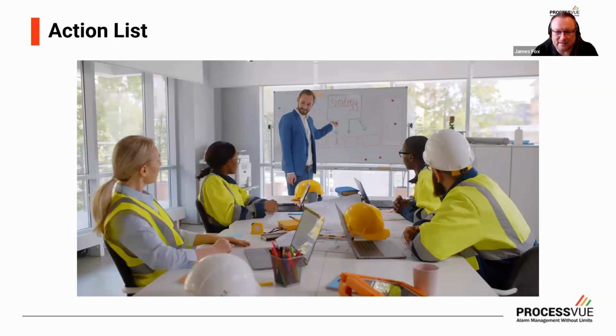But each session, as it progresses, they'll review the alarms and decide upon a number of actions and tasks associated with the alarms. So it could be you've agreed to make changes to 50 alarms, let's say, and add on delay timers for them because they're chattering alarms. After the workshop, somebody has to go and implement those changes into the host system, whether it's the SCADA system, the DCS system, or whatever system you're using.